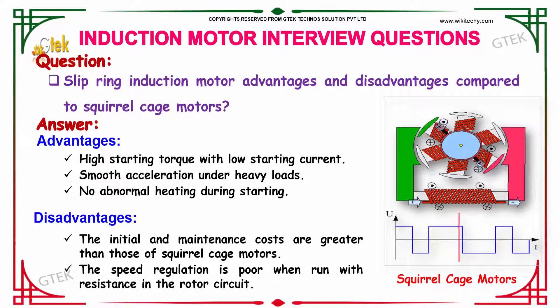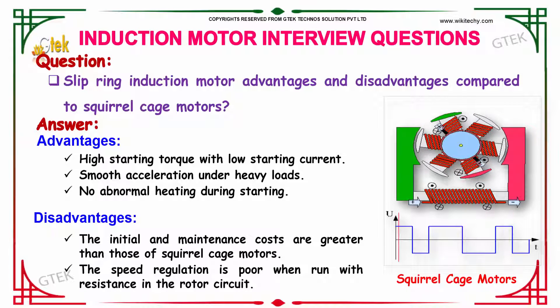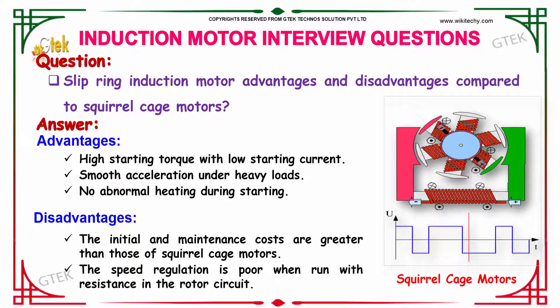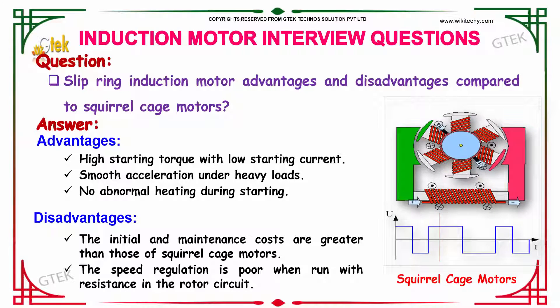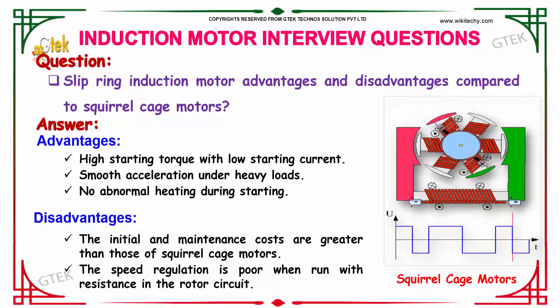We have the slip ring induction motor advantages and disadvantages, compared to squirrel cage motors. The advantages are high starting torque with low starting current, smooth acceleration under heavy loads, and no abnormal heating during starting.